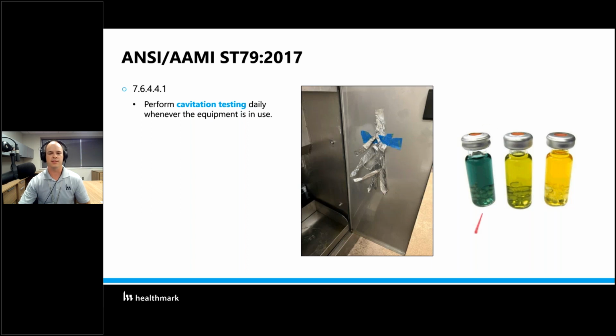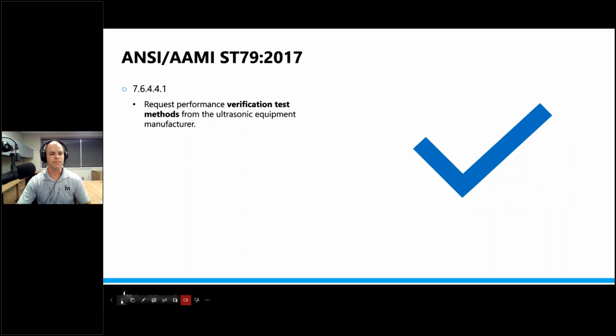So then there are tests like these on the right that you can use that just show a change in color and hopefully make testing for cavitation that much simpler. But understand what is out there and available to you in order to perform this kind of test and work accordingly or add accordingly to your procedure. So another thing it says is to request performance verification test methods from your ultrasonic equipment manufacturer. So that's something that they should be instructing you whenever you purchase a new piece of equipment, or maybe you've had your equipment for a long time, you haven't even seen your rep in a long time. It's something that we would definitely recommend that you ask them about.